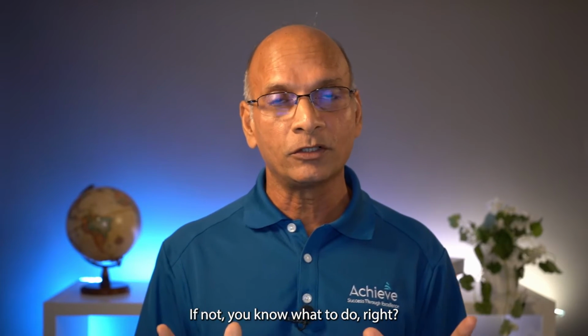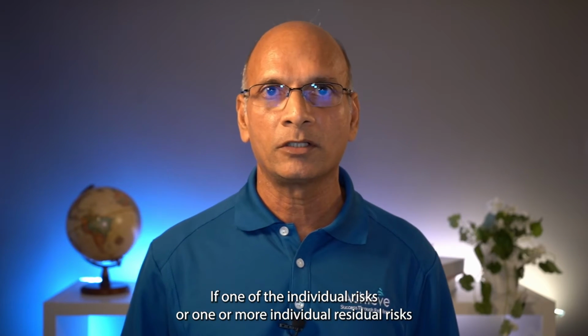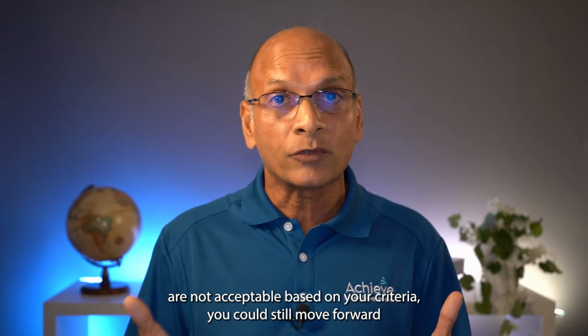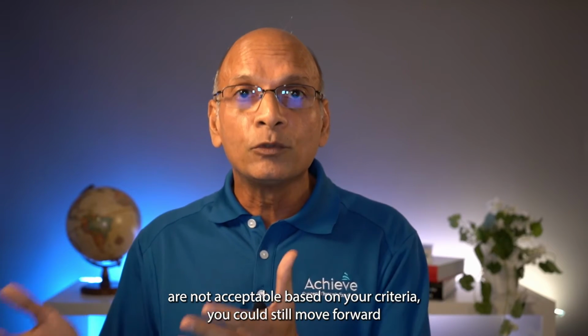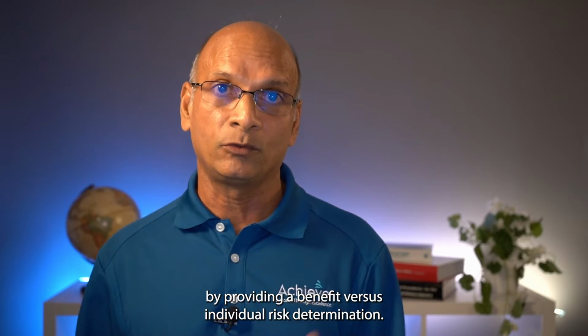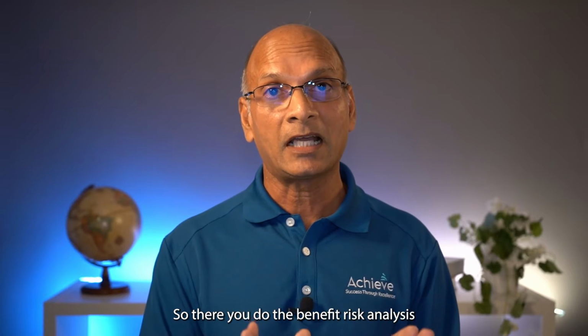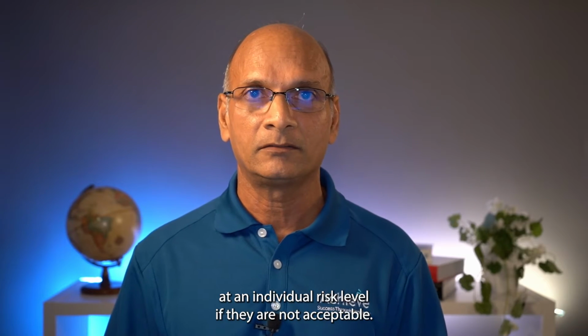If not, you know what to do, right? If one or more individual residual risks are not acceptable based on your criteria, you could still move forward by providing a benefit versus individual risk determination. So there you do the benefit-risk analysis at an individual risk level if they are not acceptable. So you could do that.